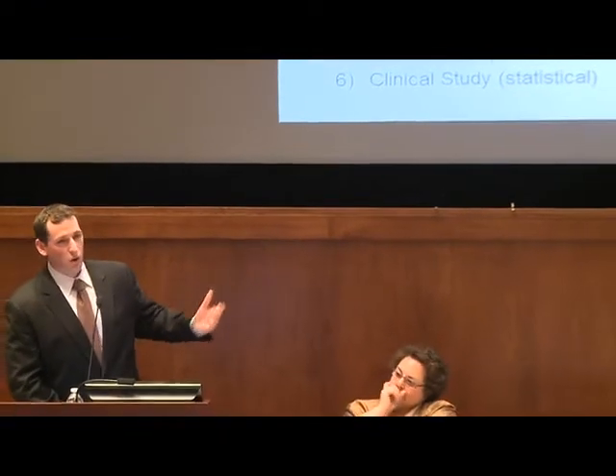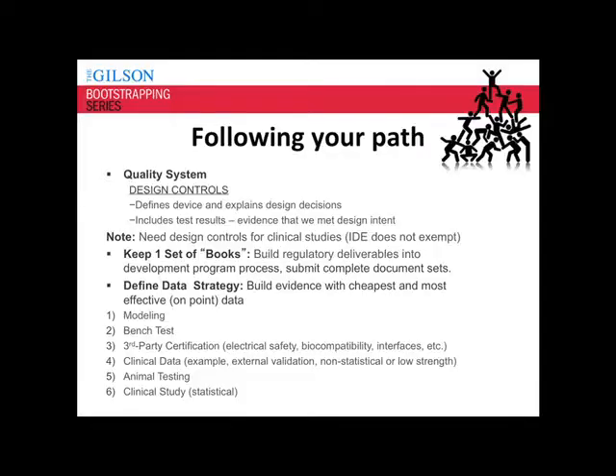Okay, so once you figure out what you are—class 1, class 2, class 3—there are certain requirements you need to follow. Everyone has to follow quality system regulations, and I would personally emphasize design controls. This is something that, having worked with taking devices into a large company, is very difficult to communicate exactly what design controls would mean, but it's essential to knowing what that device is, how it's defined, and how you're going to test it.